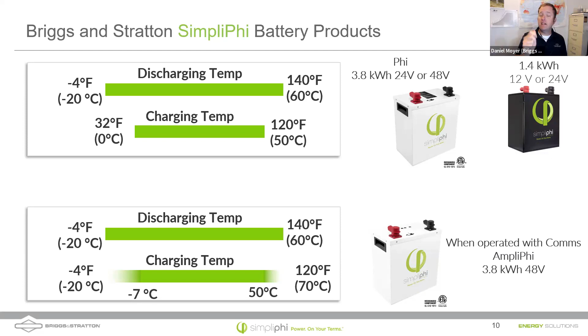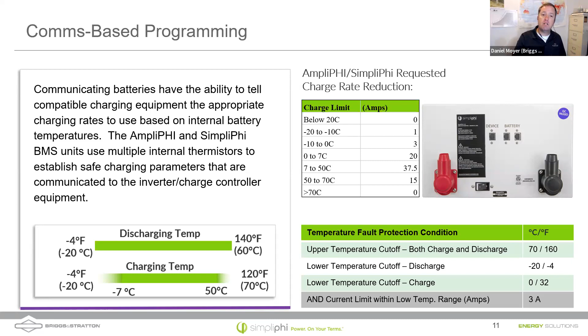This is about communication-based programming. This chart shows how the AmpliPHI battery can tell a piece of equipment that it's below a certain temperature, and the corresponding amps that should be pushed to the battery so it isn't damaged. There are temperature fault protections too—the batteries have built-in 10K thermistors, and at some point it will tell the equipment it's too cold or too hot, stop charging me, so we don't damage ourselves.